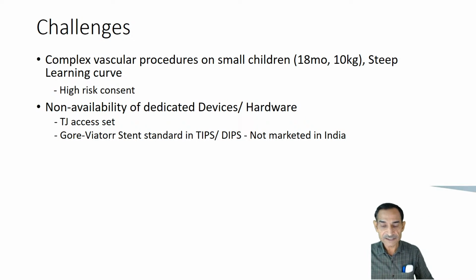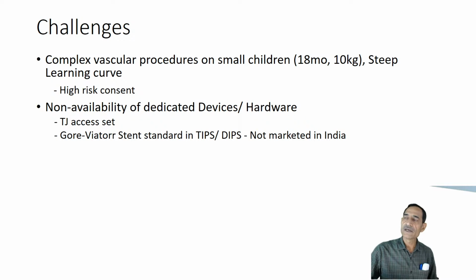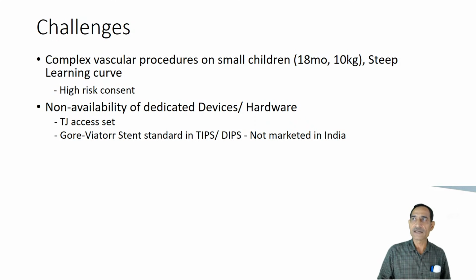Now, the other challenge is the non-availability of dedicated equipment and hardware, which is otherwise available for adults and maybe elsewhere in the world. In particular, I'm talking about two devices. One of them is a transjugular access set. The long metallic needle, if you had noted in the procedures that Dr. Madhu had shown you, that long needle which we use to access the portal vein from the neck, is almost about 40 centimeters, and a child is not very long either. So we are almost adapting adult hardware to suit the child's need, which is not appropriate actually.